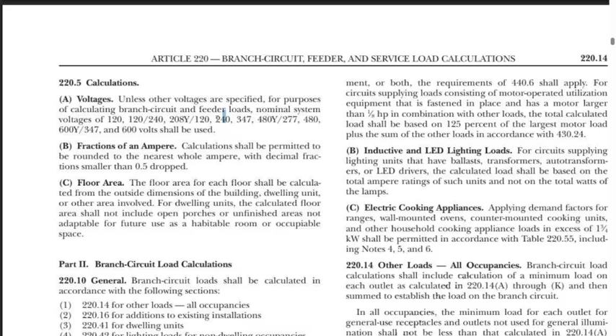Now remember the number I gave us way back - if you didn't have this highlighted, just a reminder from the 220.5 article that gave us a bunch of voltages we use in these calculations. We are only going to go with 1 from the house, which is the system we're using, the 120/240. Ultimately that's what our panel is going to provide, but just the 240 number for this calculation - that's why I had you guys highlight that single 240, just to not confuse it with the 120.